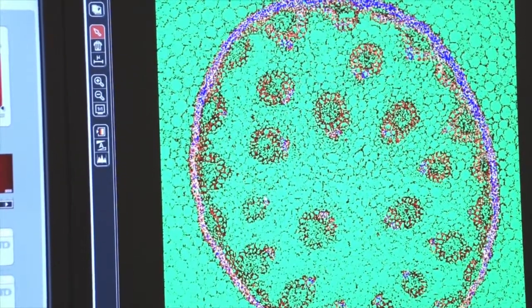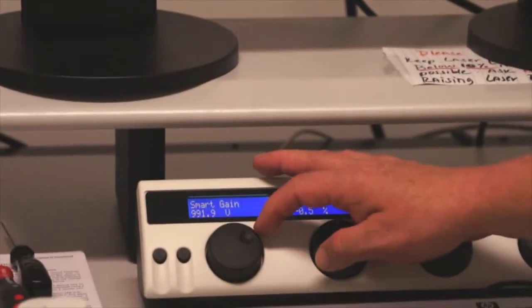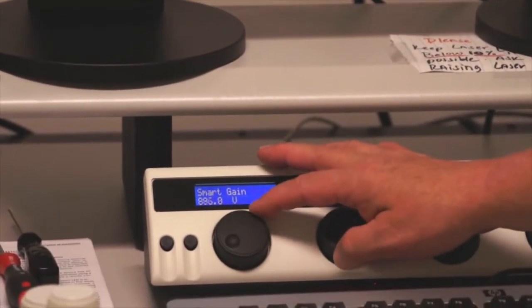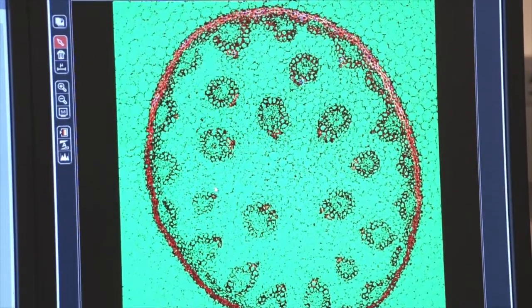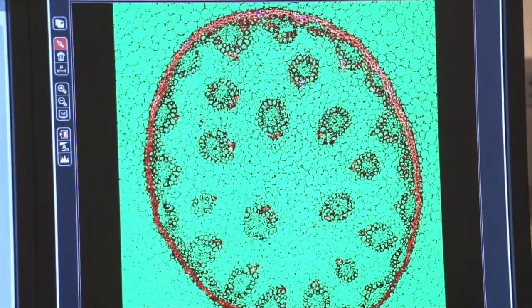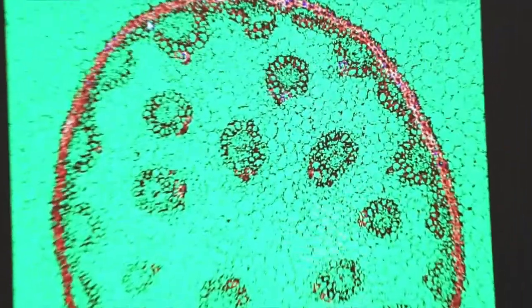Your gain control will change the number of blue pixels in your image, and you want to turn the gain down until you have only a few blue pixels. As you can see here, at about 891, I'm starting to see a few blue pixels in my image.